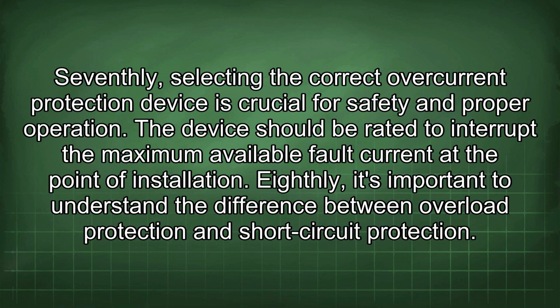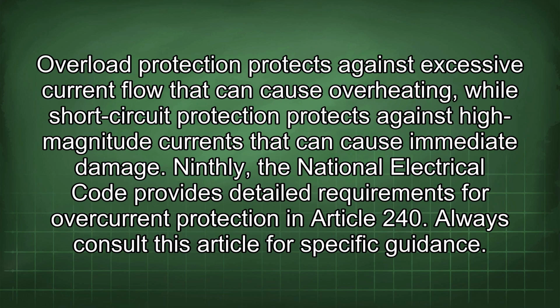Eighthly, it's important to understand the difference between overload protection and short-circuit protection. Overload protection protects against excessive current flow that can cause overheating, while short-circuit protection protects against high-magnitude currents that can cause immediate damage. Ninthly, the National Electrical Code provides detailed requirements for overcurrent protection in Article 240. Always consult this article for specific guidance.